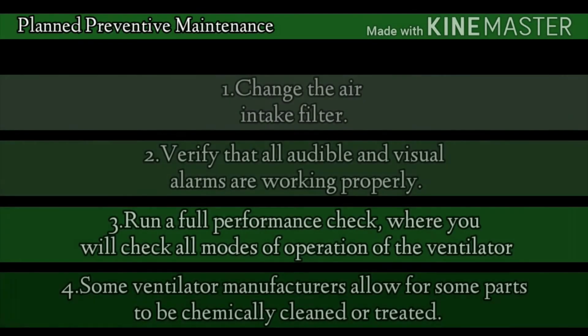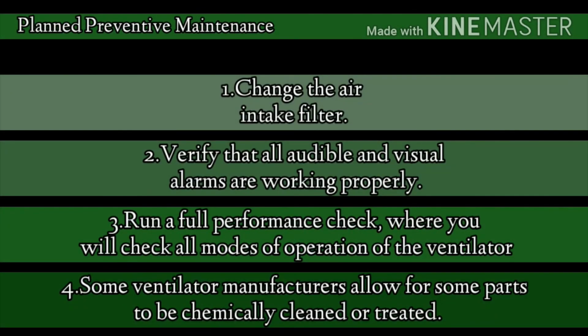Planned preventive maintenance. First, change the air intake filter. Second, verify that all audible and visual alarms are working properly. Third, run a full performance check where you will check all modes of operation of the ventilator. Lastly, some ventilator manufacturers allow for some parts to be chemically cleaned or treated.